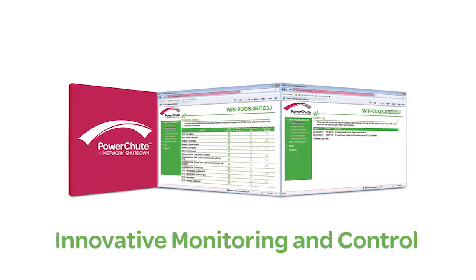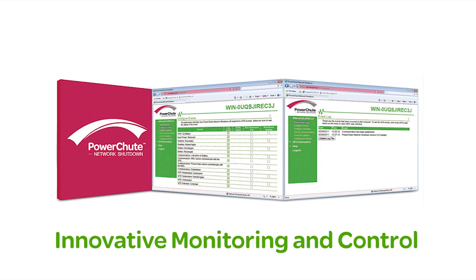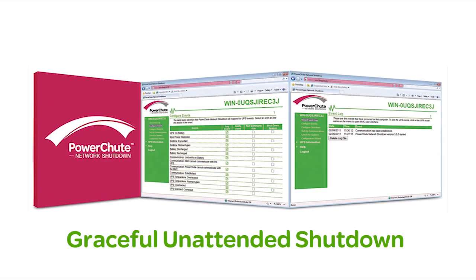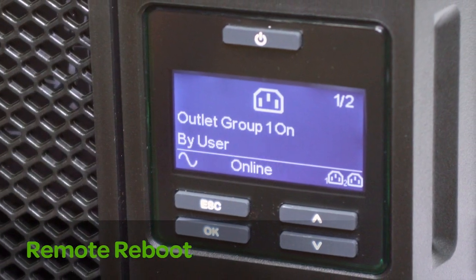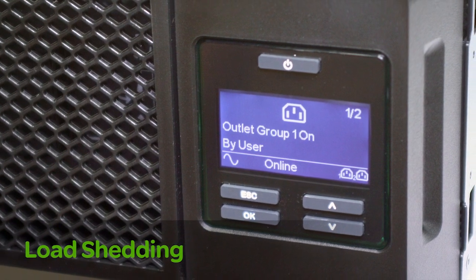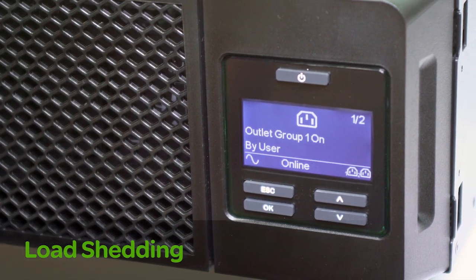PowerChute provides innovative monitoring and control as well as graceful unattended shutdown in extended outage situations over the network. Switched outlet groups can be individually controlled to customize settings and provide for discrete reboot of hung devices, sequenced on-off and non-critical load shedding to preserve on-battery runtime.